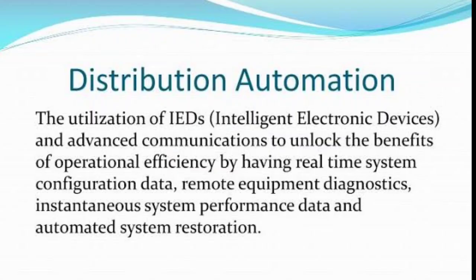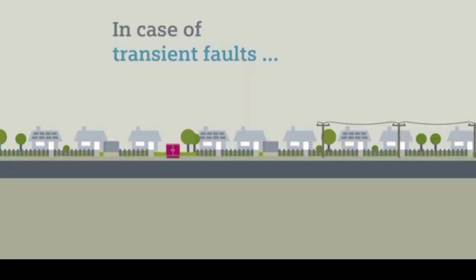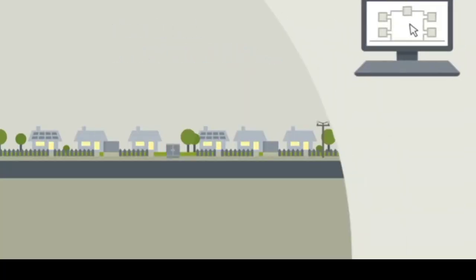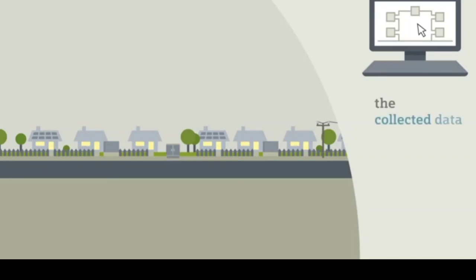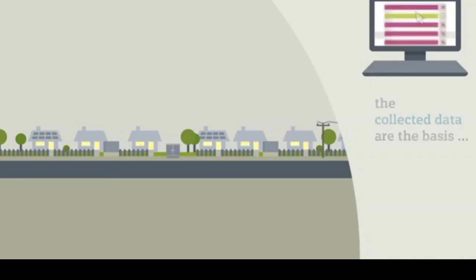Majorly, Distribution Automation is a family of technologies including sensors, processors, communication networks, and switches that can perform a number of distribution system functions — not only fault detecting, fault isolation, and giving feedback to the system, but also power factor correction can be done by using Distribution Automation.